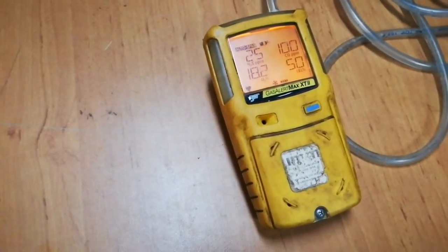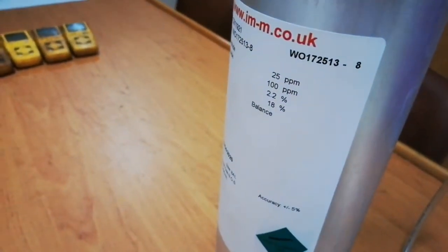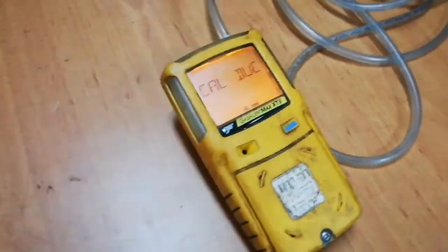I've already opened the span gas cylinder. Here you can see the reading, and this reading should be the same as the figures written on the span gas cylinder. Here you can see hydrogen sulfide 25 ppm, carbon monoxide 100 ppm—same figures you can see here. Once the calibration is done, you'll see this message.